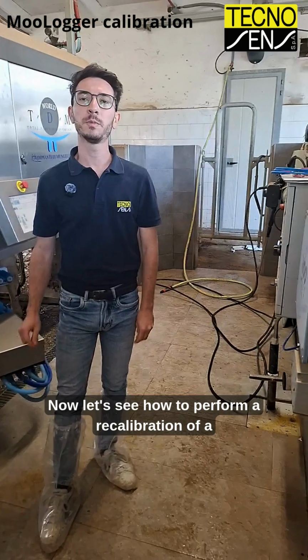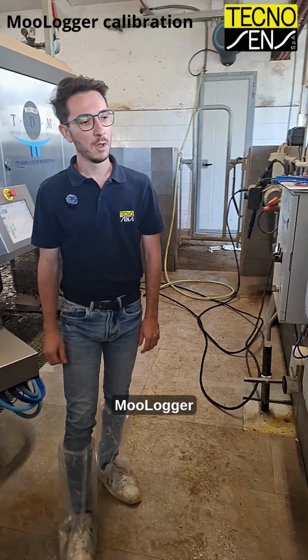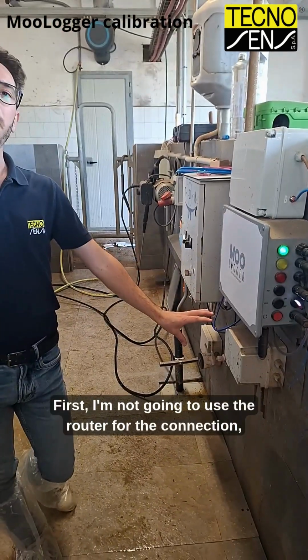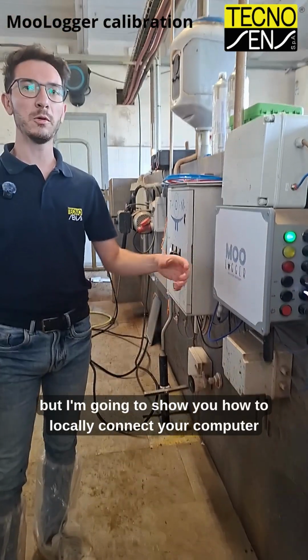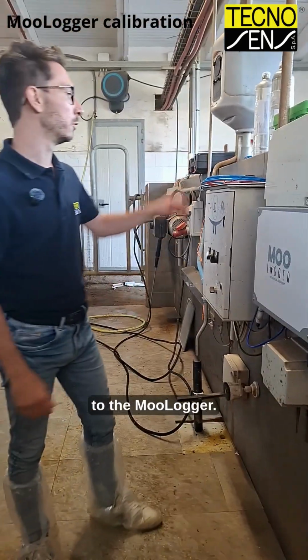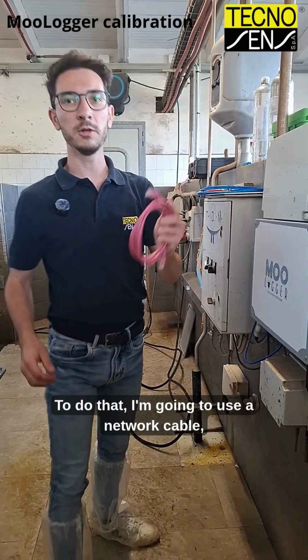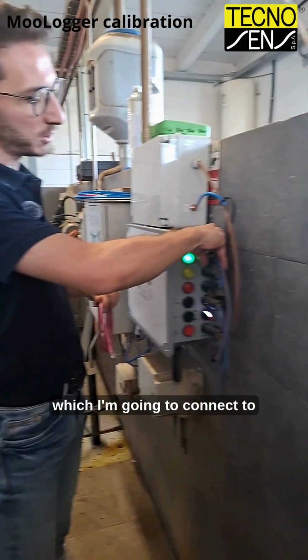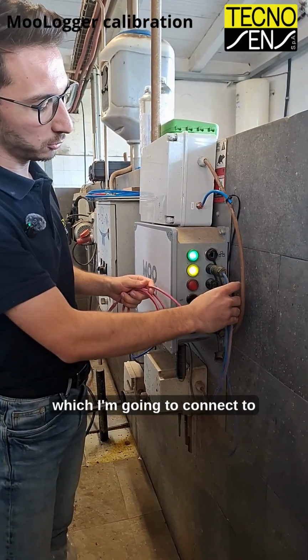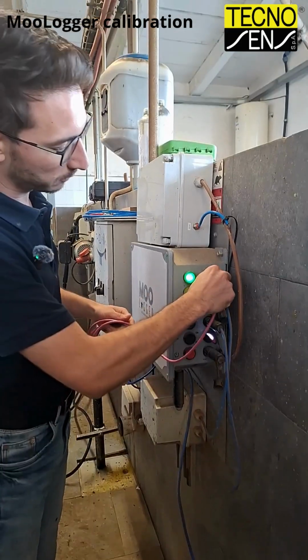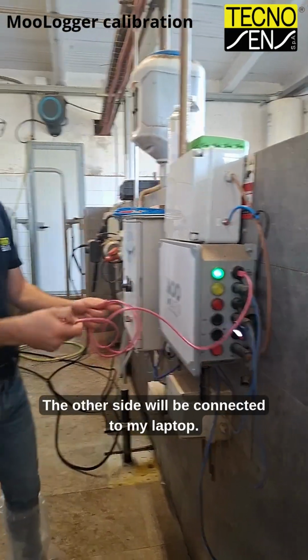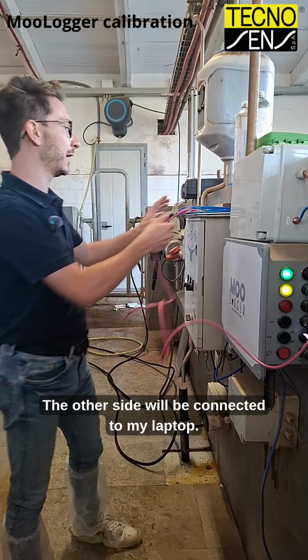Now let's see how to perform a recalibration of a MooLogger. First, I'm not going to use the router for the connection, but I'm going to show you how to locally connect your computer to the MooLogger. To do that, I'm going to use a network cable, which I'm going to connect to the network inlet. The other side will be connected to my laptop.